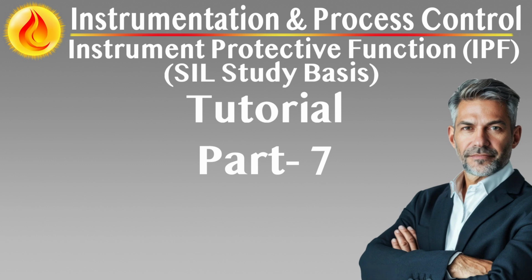Unlike manual proof tests, automatic testing operates in the background, detecting faults in real time, improving safety availability, and reducing the exposure window to undetected dangerous failures. When implemented correctly, automatic testing significantly enhances the overall reliability of IPFs by shortening the interval between failure occurrence and detection. It also reduces the burden on maintenance personnel, improves SIL compliance, and enables predictive maintenance strategies.